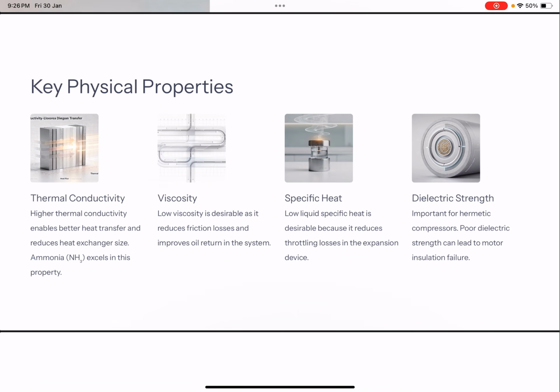Low viscosity is desirable as it reduces friction, and hence it reduces frictional losses. If the viscosity is lower, the friction is lower, and if the friction is lower, the losses would be lower. So a low viscosity refrigerant is always desirable, and it would also improve the oil return in the system. High thermal conductivity and low viscosity are thus the key physical properties. Lower specific heat, lower liquid specific heat, is desirable because it reduces the throttling losses in the expansion device.